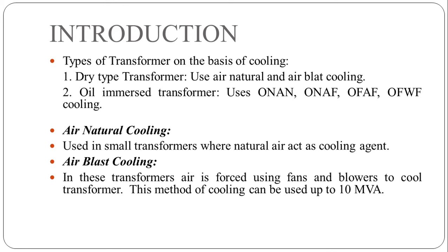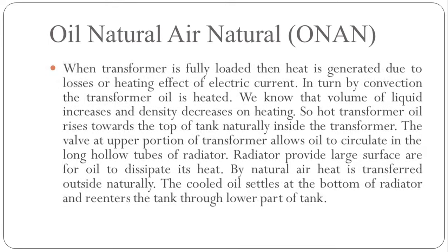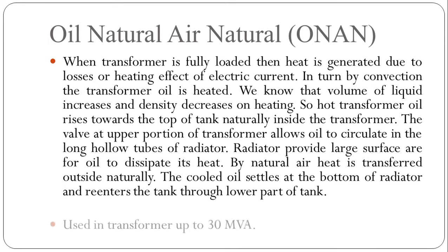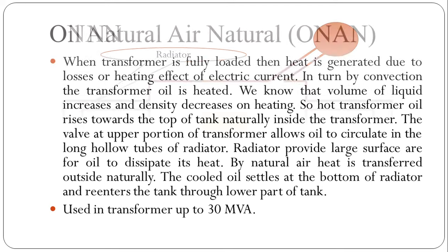Air blast cooling can be used up to 10 MVA. Now we will discuss the cooling methods of oil immersed transformers. The first is oil natural air natural cooling, which is used up to 30 MVA. This cooling scheme has been discussed in a previous lecture, but let's revise the concept.